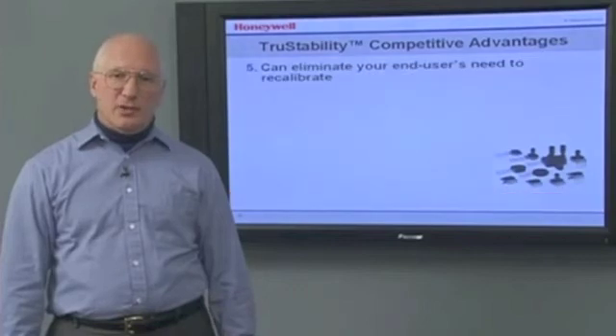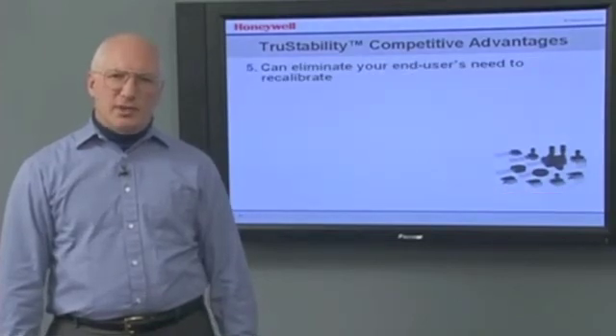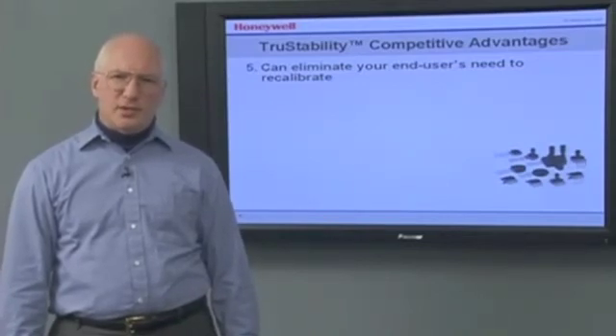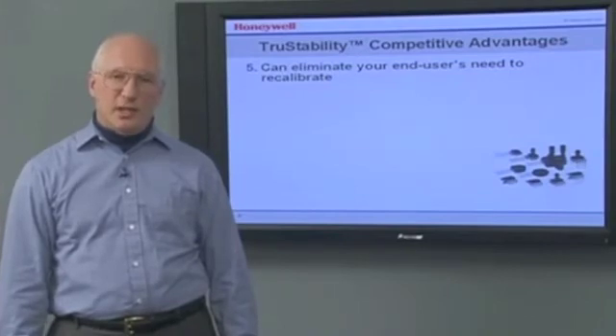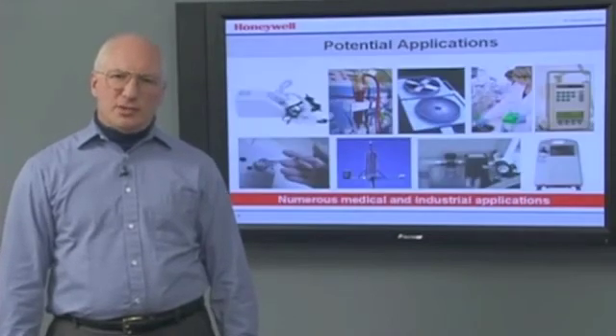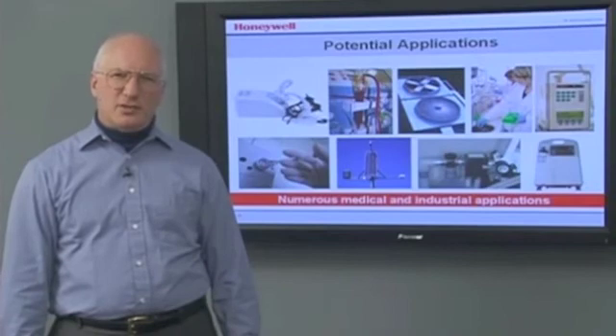They can eliminate your end-user's need to recalibrate. Stability is not only important to you — it's important to your end-user. Because a user typically doesn't know when a system needs to be recalibrated, common practice is to recalibrate prior to each use. This results in a need to build recalibration capability into your design, requiring engineering resources and increasing costs. When a TruStability Sensor is used, frequent recalibration is not necessary, simplifying your design and making it easier to use. TruStability Sensors can potentially be used in a number of medical and industrial applications.